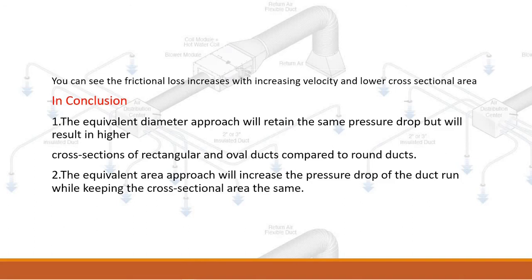In conclusion: one, the equivalent diameter approach will retain the same pressure drop but will result in higher cross-sections of rectangular and oval ducts compared to round ducts. Two, the equivalent area approach will increase the pressure drop of the duct run while keeping the cross-sectional area the same.